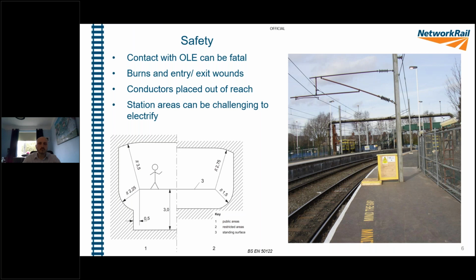And what we've come to in the UK particularly is two different requirements on distances for safe distances. One of those, as shown on the left diagram, is for public areas, on number 1, which is a 3.5 metre distance from a standing surface. It's important to note that this is to any of the electrical equipment. So it's not only the contact wire, but it could be any part of the overhead structure that is oversailing a platform. For example, seen on the picture on the right, to the left of the insulators, you can see that there are live parts of that cantilever frame still over the platform. It's important that 3.5 metres is maintained, which in this particular instance, it has not been.